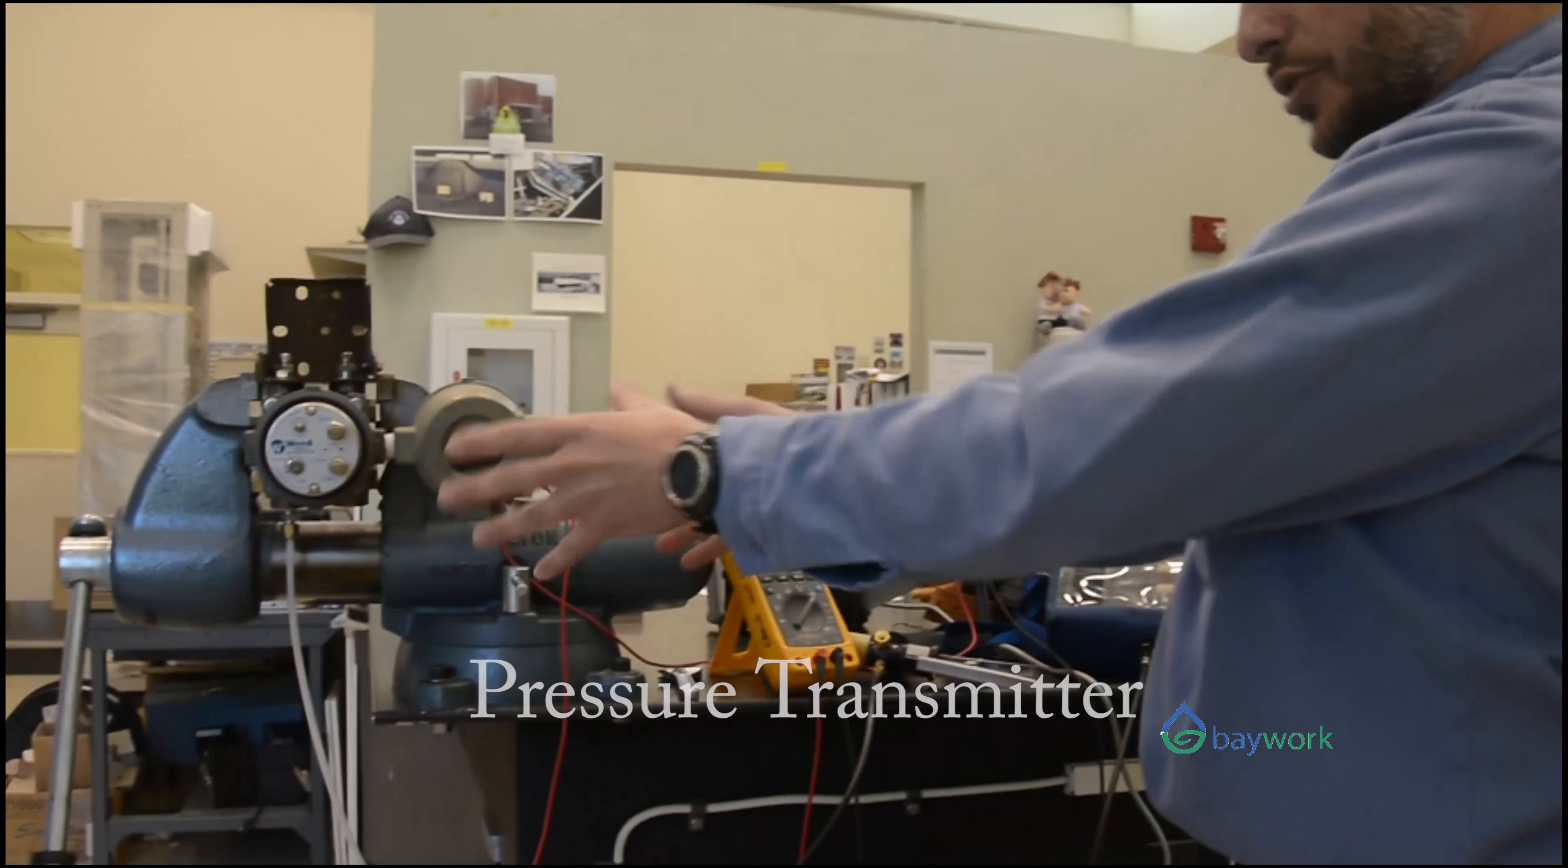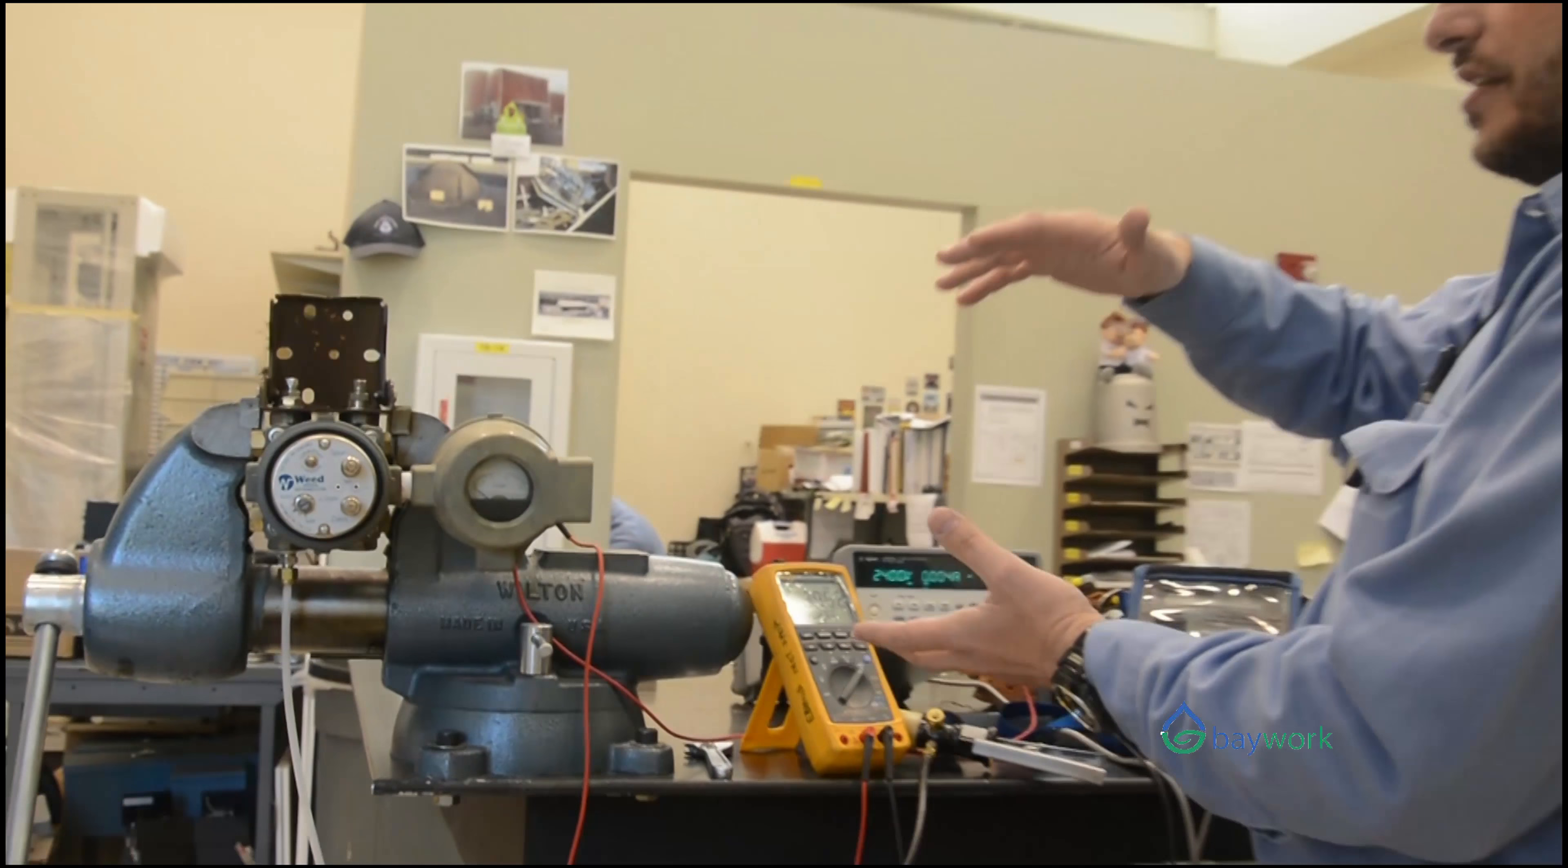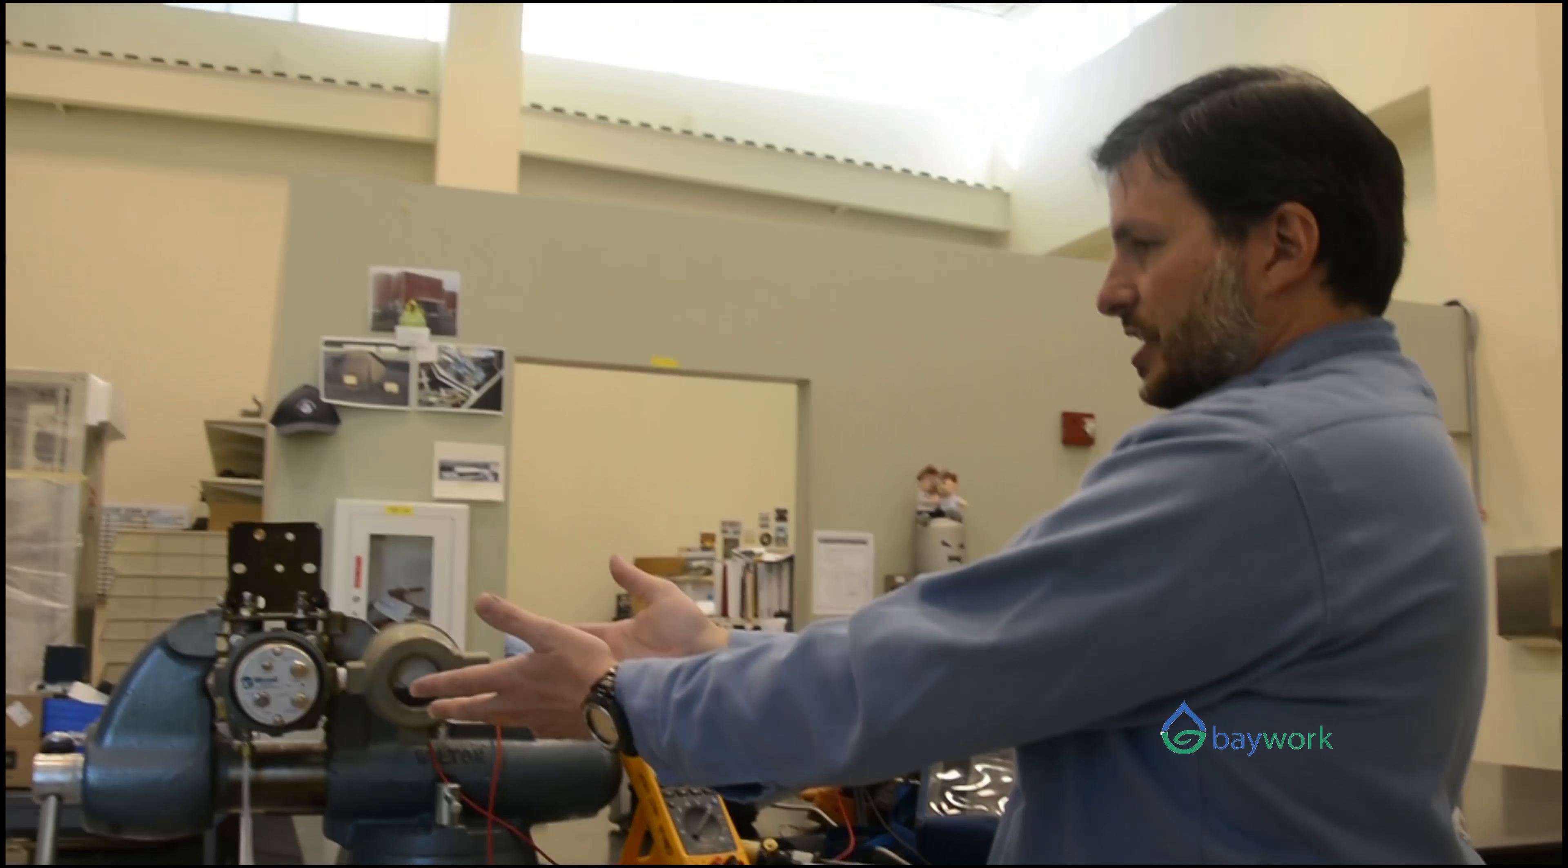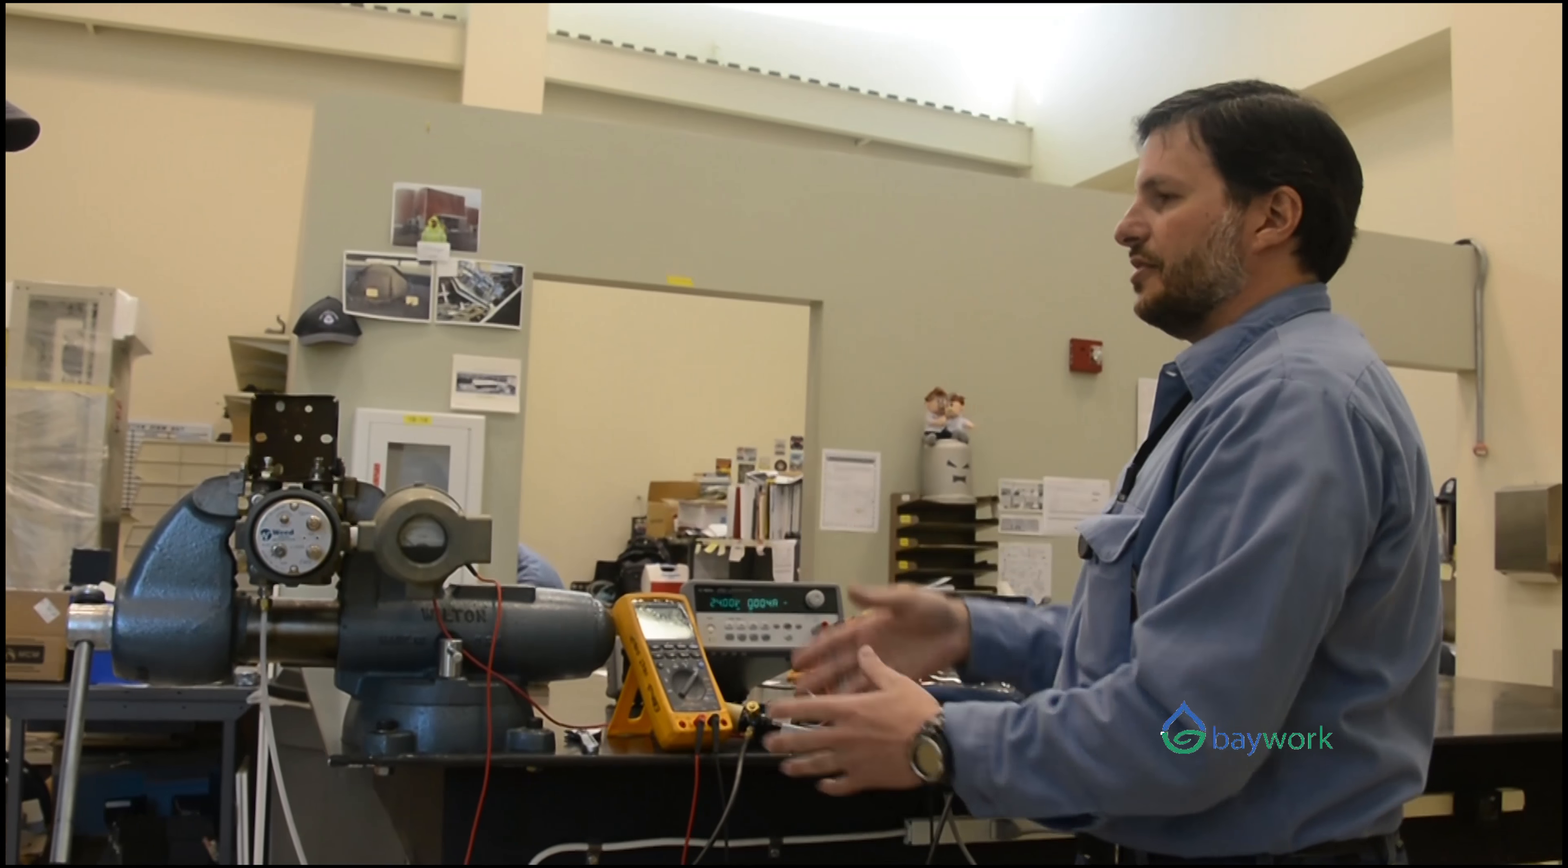This is actually a pressure transmitter, right? Right. And what we're doing is measuring levels. So the transmitter is seeing pressure at the bottom of the tank and the higher the level of the tank, the more pressure it's going to see. Right. So the transmitter is going to be converting that into a milliamp current signal. That's why you've got this milliamp meter and the power supply there.